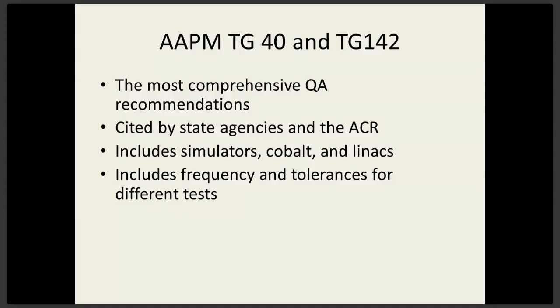So here are the money slides. On a daily basis, X-ray constancy should be within 3%. In other words, the output day-to-day should not vary by more than 3%. That's for daily warm-up, for daily checking. That's not for physicists. Physicists are kept monthly to a stricter percentage, but daily can be up to 3%. Lasers within 2%, ODI within 2 millimeters, and the door interlock and the audio-visual controls absolutely have to work on a daily basis, or you cannot treat the patient.